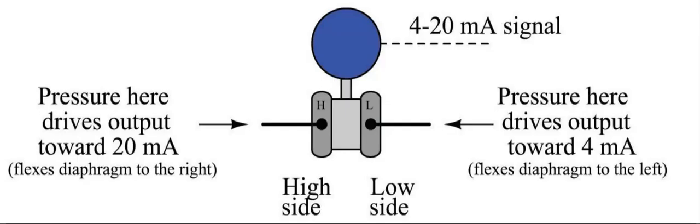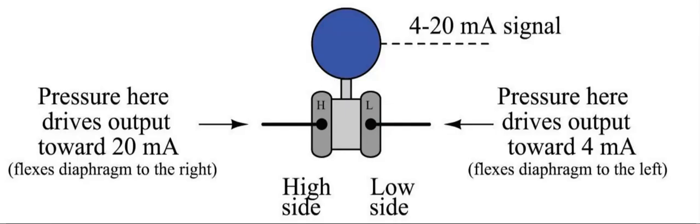The reason that it's 4 milliamps is so that if you have an error with your zero point, you won't think everything's okay when the system is outputting zero. It has an elevated signal of 4 milliamps so that if there's a problem with the zero point, this will drift below 4 milliamps and it'll be an indication to the operator that there is an electrical problem. That's why it's not zero to 20 milliamps. For a system where the differential pressure is zero, the transmitter will output 4 milliamps.